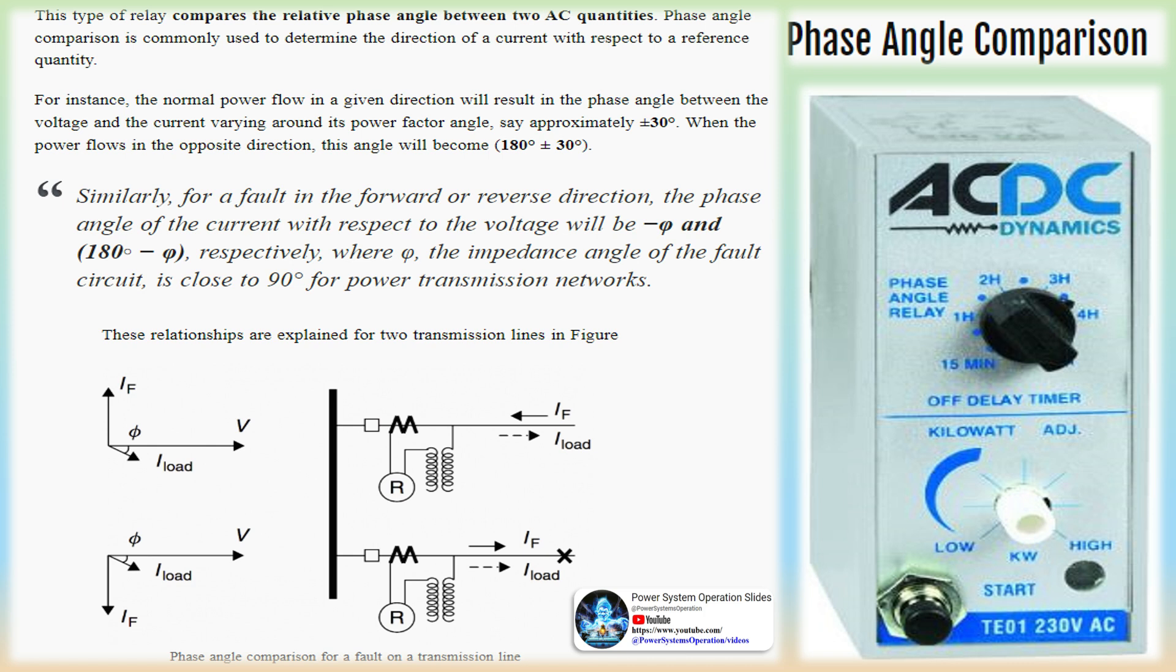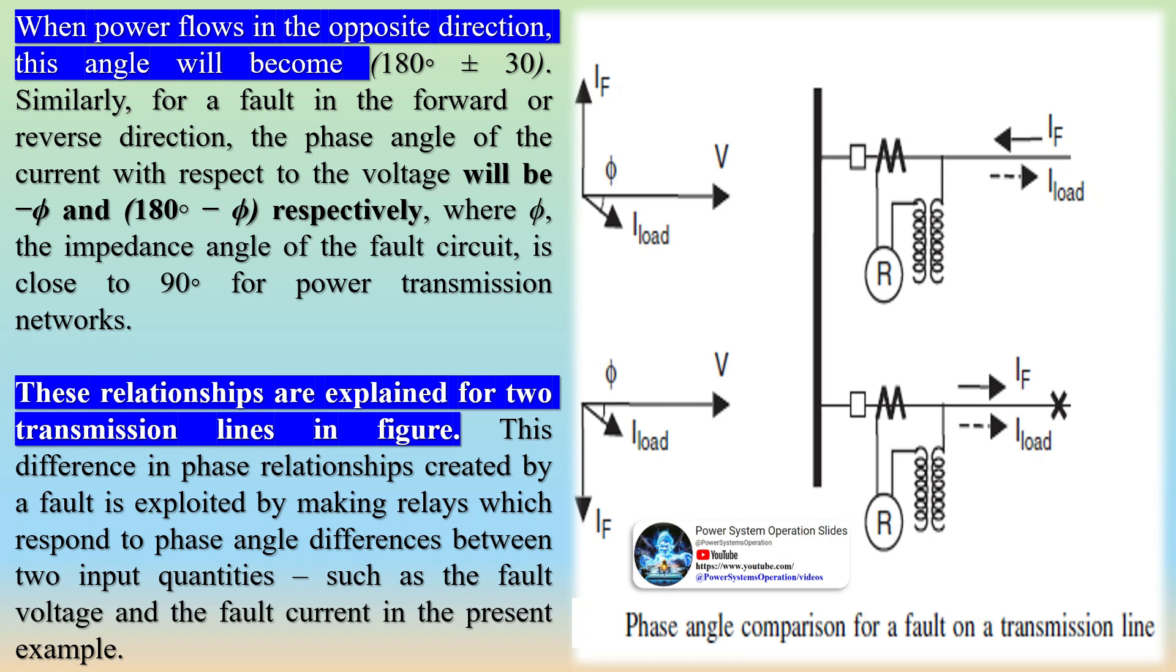Phase angle comparison. This type of relay compares the relative phase angle between two AC quantities. Phase angle comparison is commonly used to determine the direction of a current with respect to a reference quantity. For instance, the normal power flow in a given direction will result in the phase angle between the voltage and the current varying around its power factor angle, say approximately ±30°.